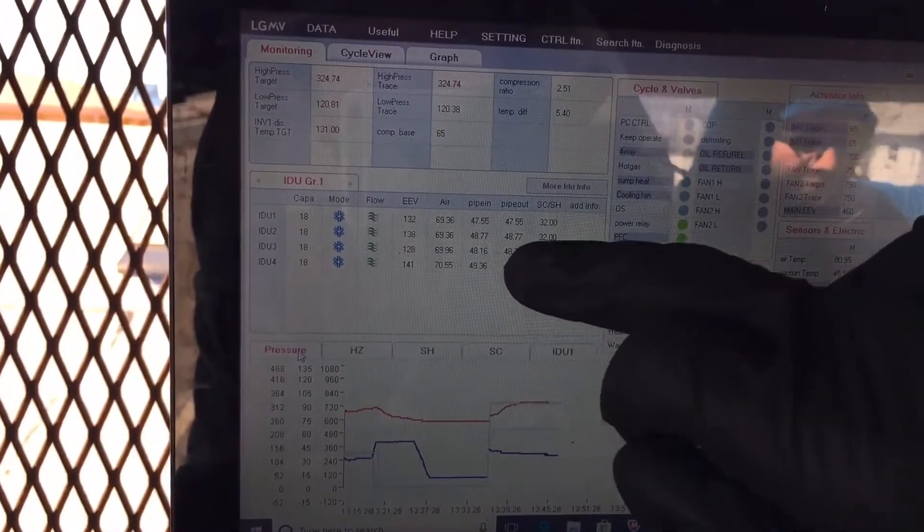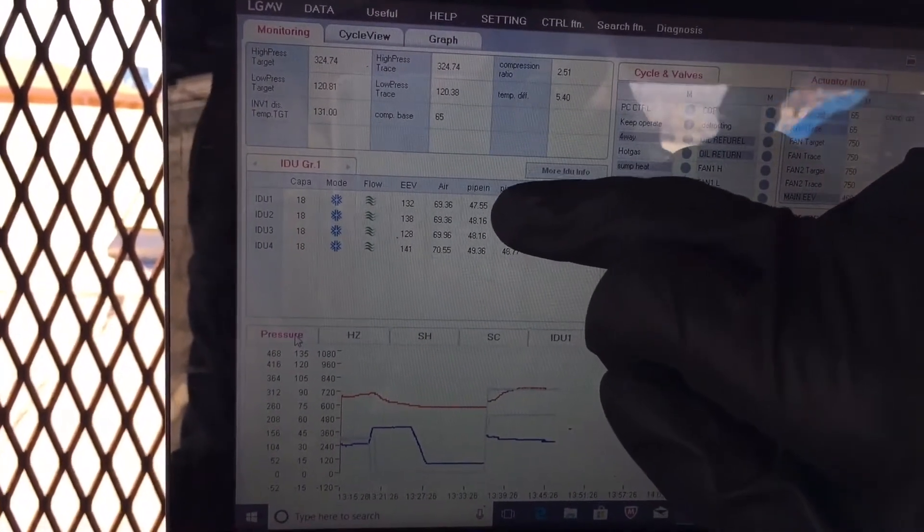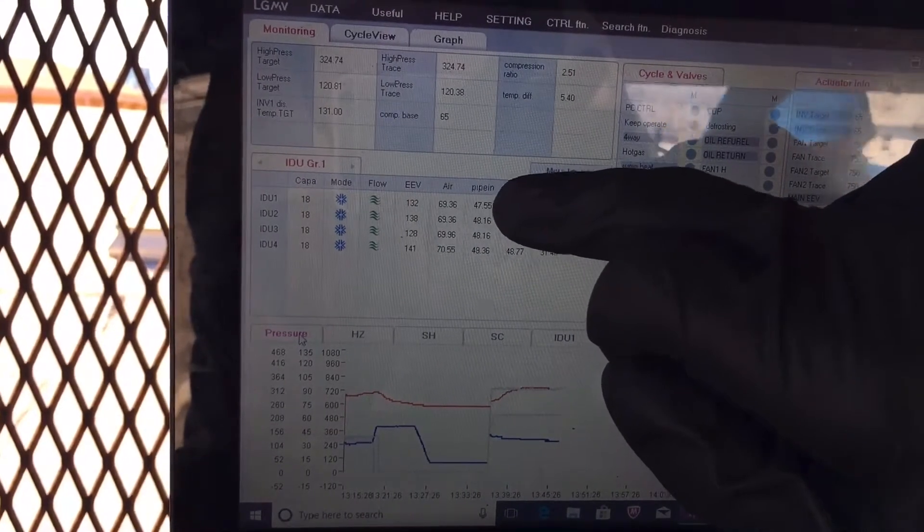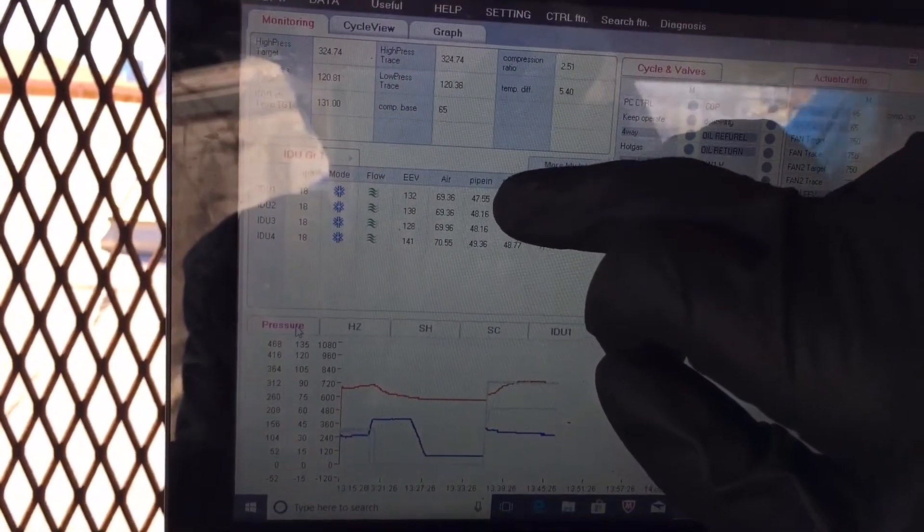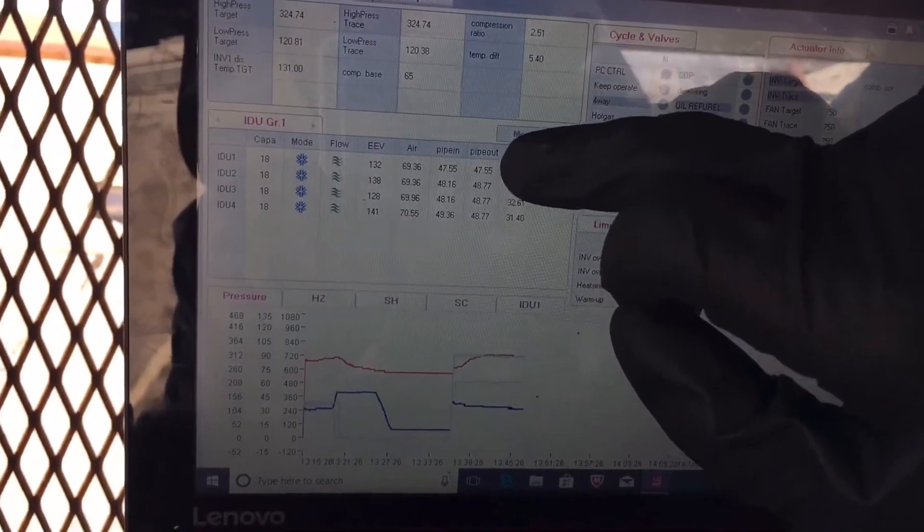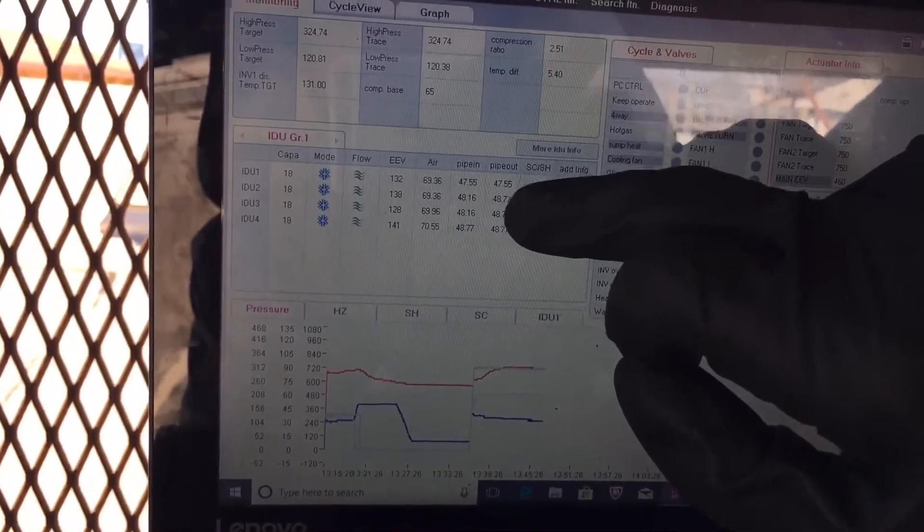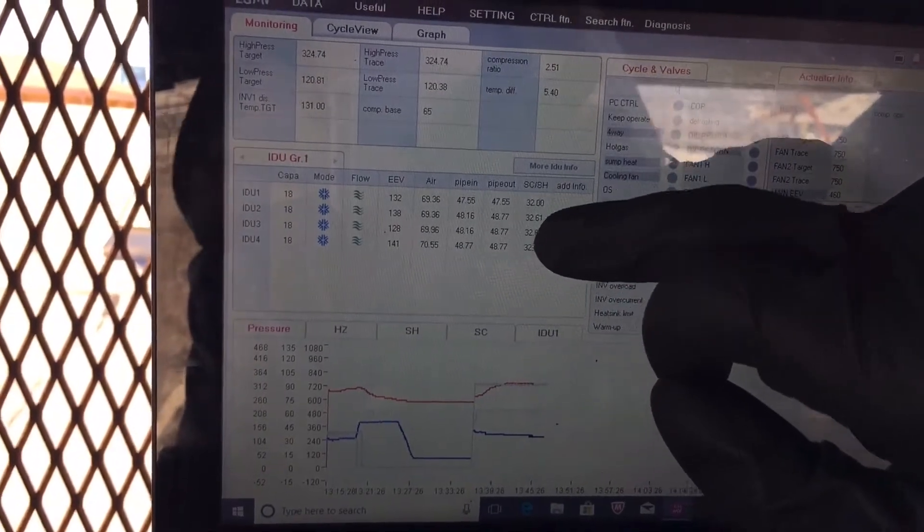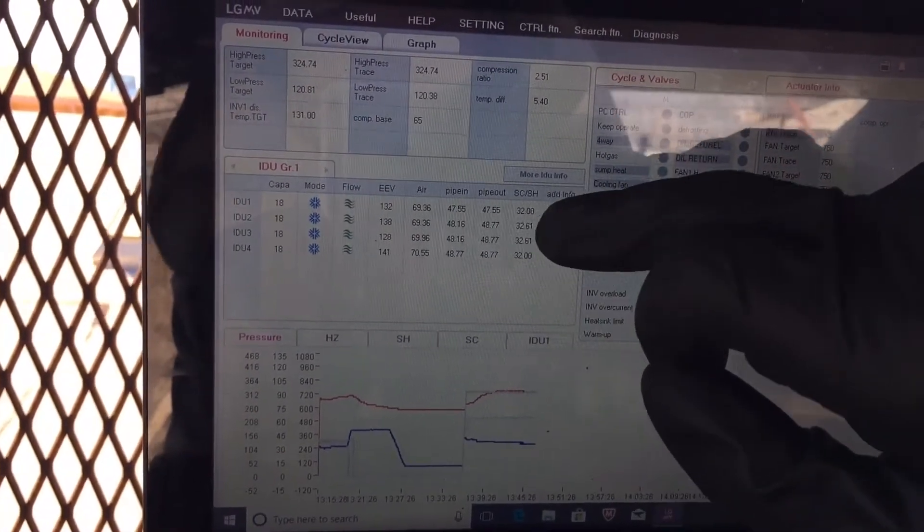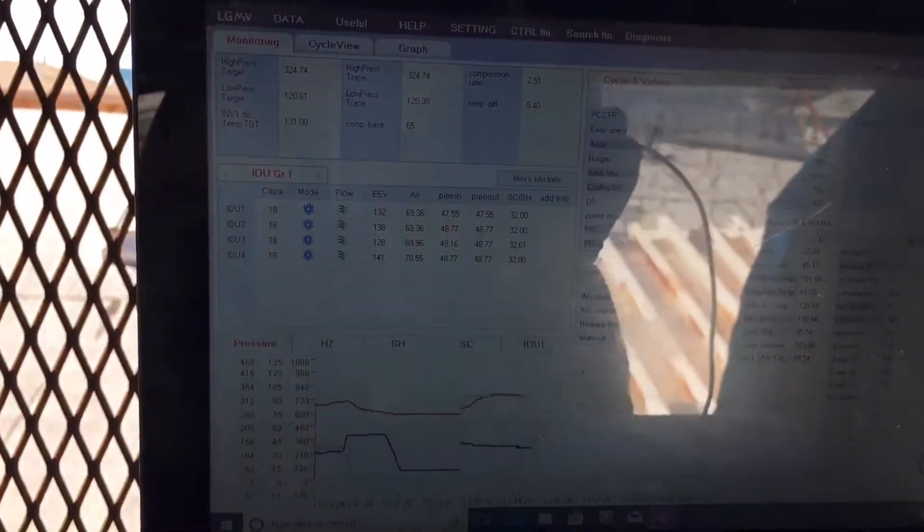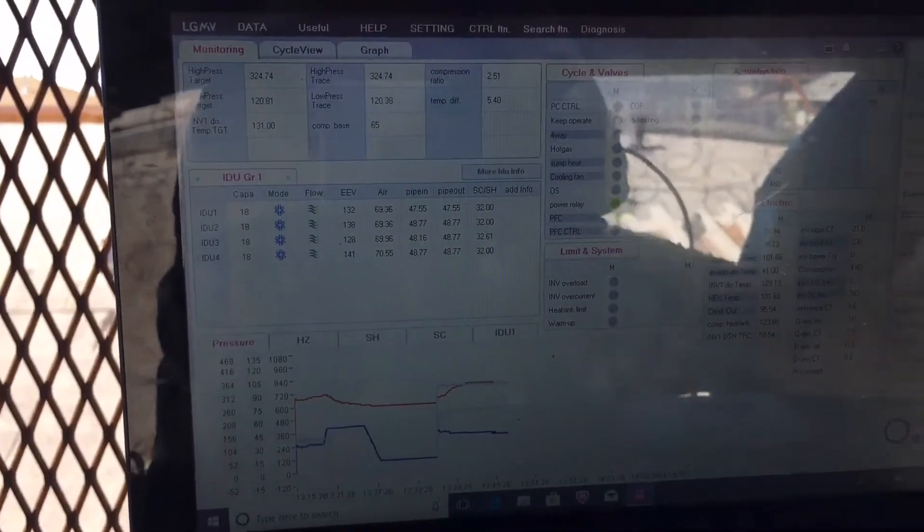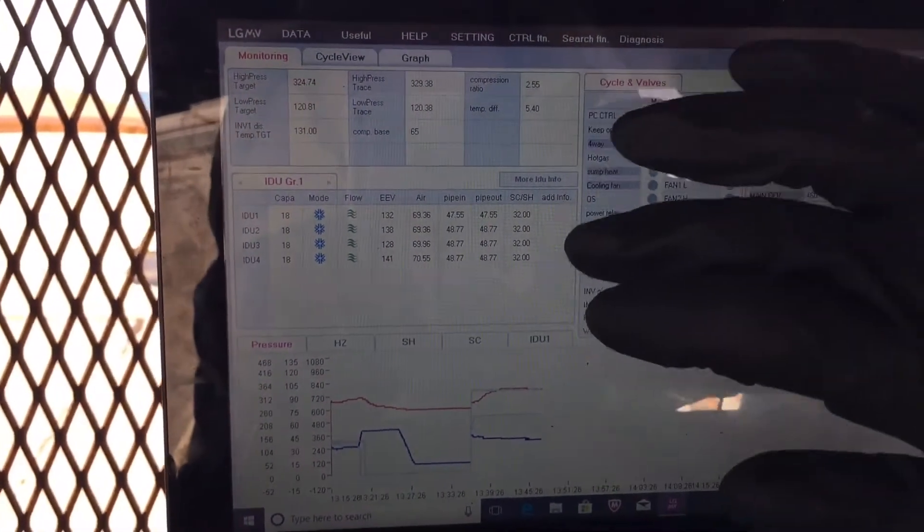Here is the temperature refrigerant in and out. See where it says pipe in? That's the actual temperature of the refrigerant entering the air handler, the evaporator inside the room. Then pipe out, that's the actual temperature of refrigerant leaving. So you'd say, what's our superheat? We're dead-on even. So most guys go, 'there's something wrong, we have no superheat, there must be something wrong.' No, there's no problem.